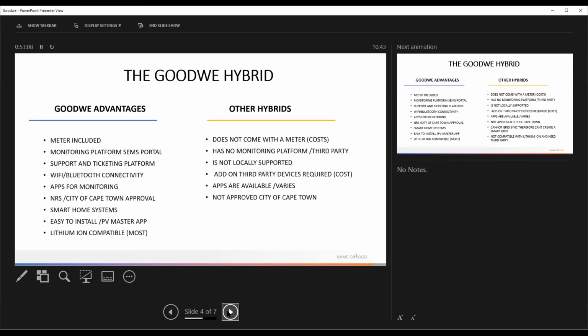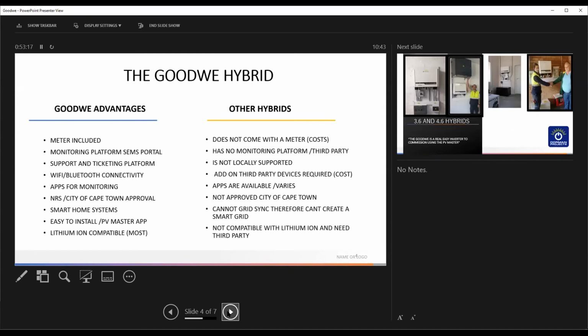The meter sits upstream, just below the supply meter. Other hybrids that don't have that meter are traditionally only able to connect with the loads on output, in other words the backed-up loads. With GoodWe, we can create this virtual grid, with the meter being the most critical part and the inverter able to grid sync. That becomes a very important tool for giving a homeowner or small business an energy solution. Other inverters often can't grid sync, so they can't export into the grid.